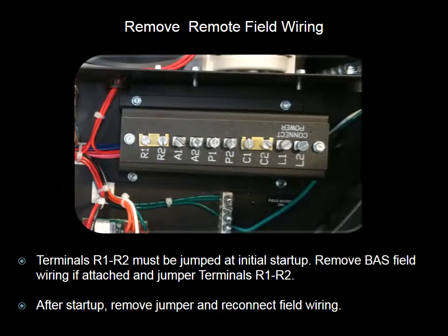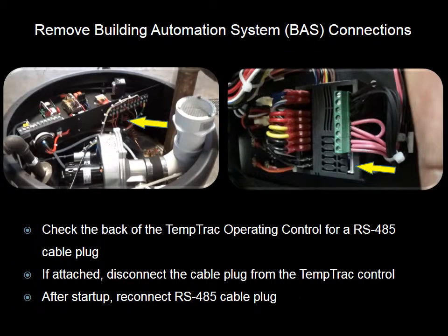When first starting up the water heater, the heater must be isolated from any remote controlling device. On the field access terminal strip, check to see if terminals R1 and R2 are jumped. If they are, nothing more needs to be done. If the terminals are not jumped but have wires connected to them, this indicates that a remote on-off relay is controlling the water heater from the building automation system. These wires must be removed and the terminals must be jumped. Remember to remove the jumper and reconnect the remote wires after startup is complete.